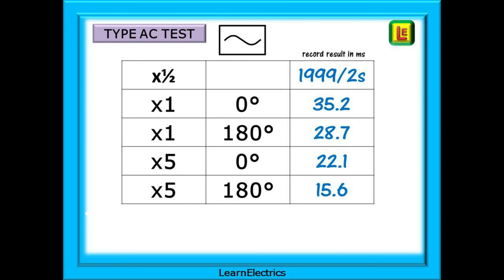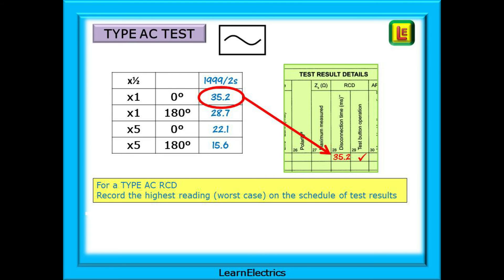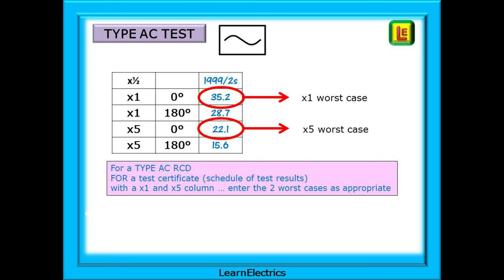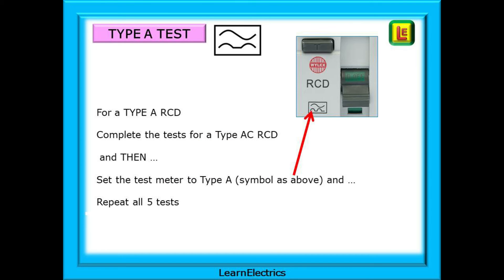This chart shows the five tests and some typical test results in blue. For the times half test of the rated current the meter holds the test signal for two seconds and the RCD should not trip — many meters show 1999 milliseconds, the most they can display, which is equivalent to two seconds. Then a times one at zero degrees and 180 degrees, and a times five at zero and 180 degrees as well. Choose the worst case tripping time — the biggest number — and record this on the schedule of test results along with a tick to show the test button works. Some test certificates by NAPIT, NICEIC etc. will have two columns for the tripping time — a times one column and a times five column — in which case choose the worst case for each.